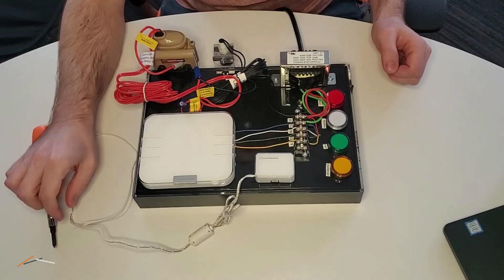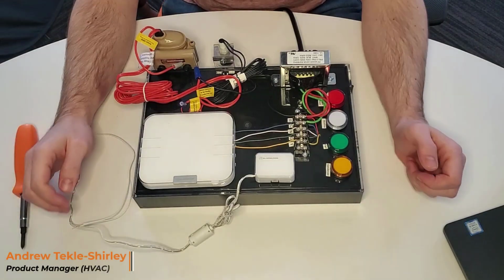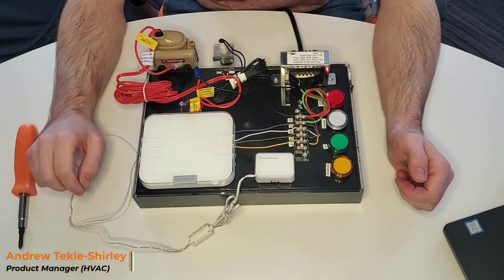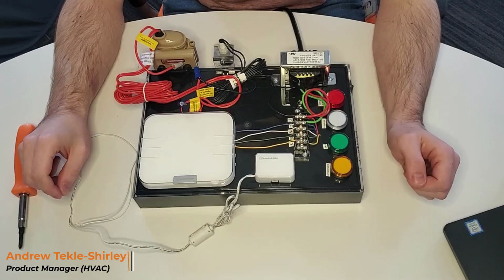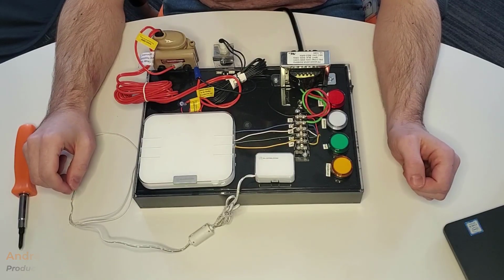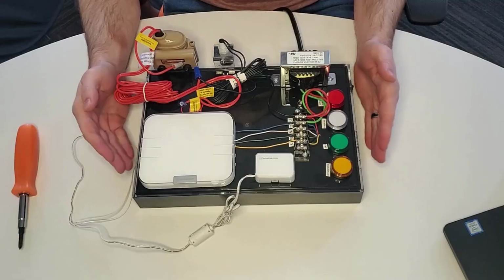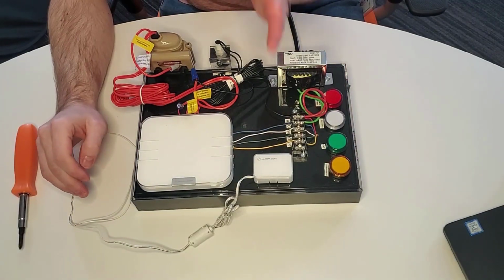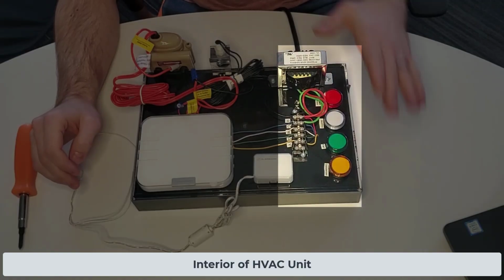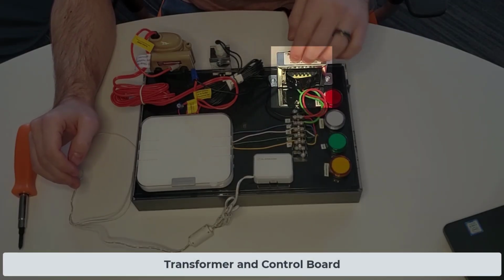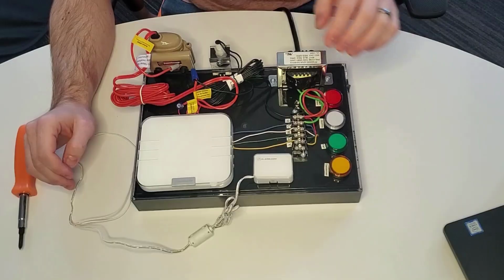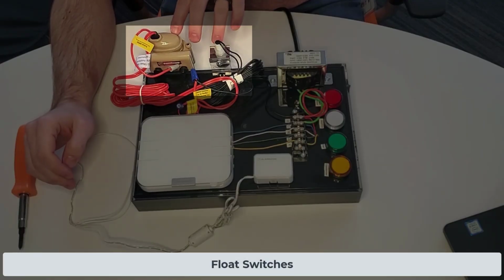We are going to review how to install the Alarm.com dry contact sensor to monitor float switches on an HVAC system. Here we have a little test board. If you imagine this section being everything inside the HVAC unit, transformer and control board. Here we have 2 float switches wired in series and then a thermostat.